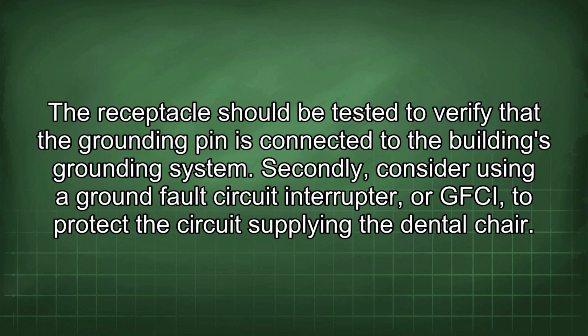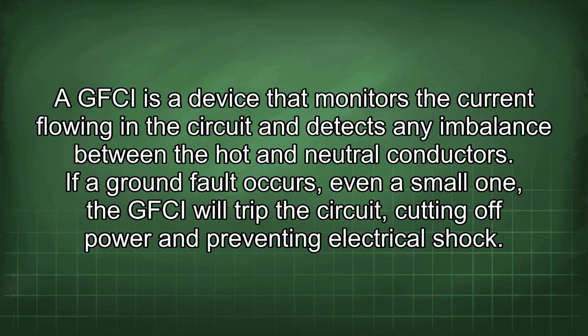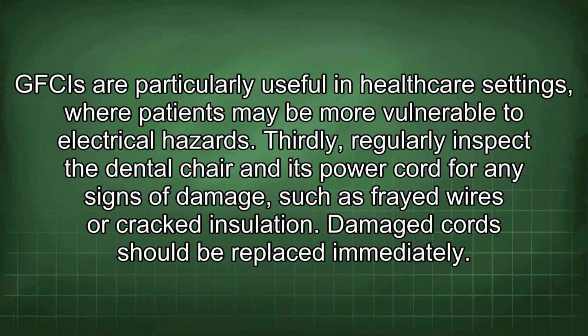Secondly, consider using a ground fault circuit interrupter, or GFCI, to protect the circuit supplying the dental chair. A GFCI is a device that monitors the current flowing in the circuit and detects any imbalance between the hot and neutral conductors. If a ground fault occurs, even a small one, the GFCI will trip the circuit, cutting off power and preventing electrical shock. GFCIs are particularly useful in healthcare settings, where patients may be more vulnerable to electrical hazards.